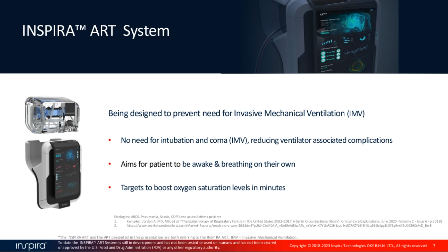So, for example, the INSPIRA ART, the way it's designed is basically removing oxygen, removing CO2 and oxygenating the blood. But in order to do this in a controlled manner, you need to know what's happening within the blood at every given time to provide safety. And so we developed a blood sensor. And here's an example of the blood sensor. So we took the blood sensor that's in the INSPIRA ART and we've turned this into a standalone product. And what it is, basically you've got a tube with blood flowing through it, and you place the sensor, it clips over the tube.